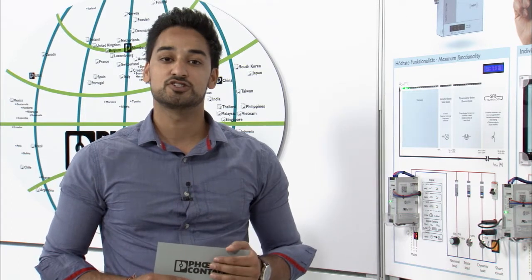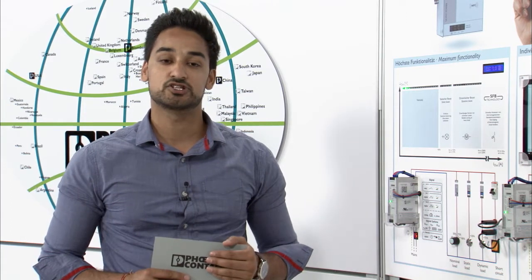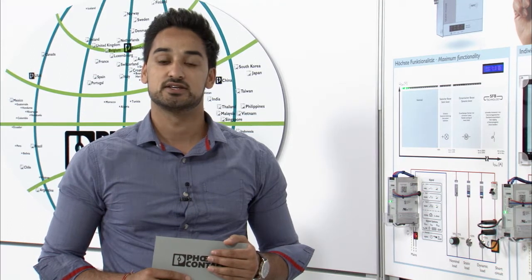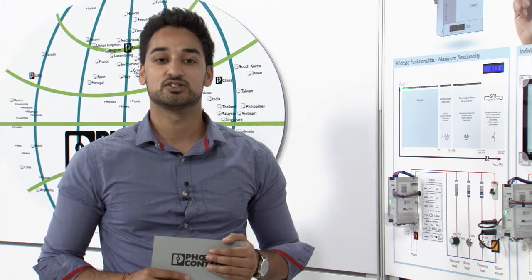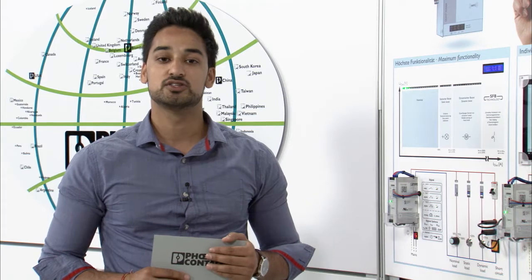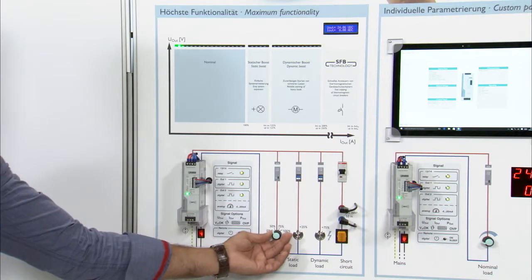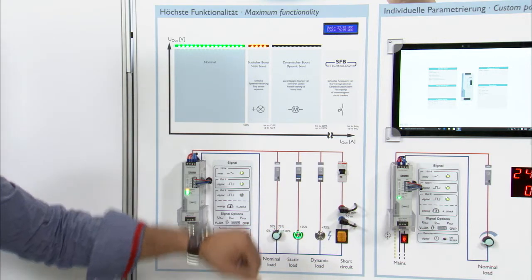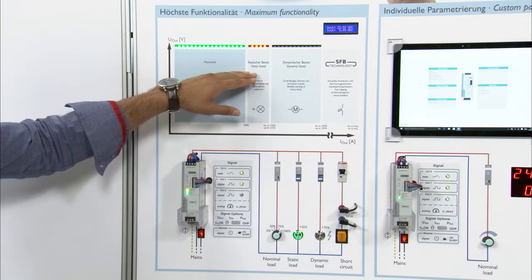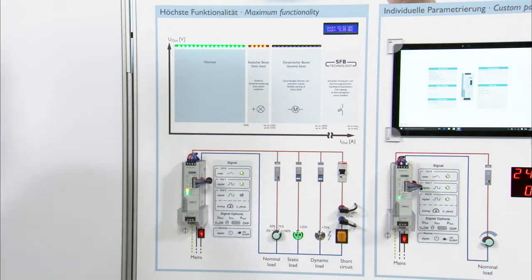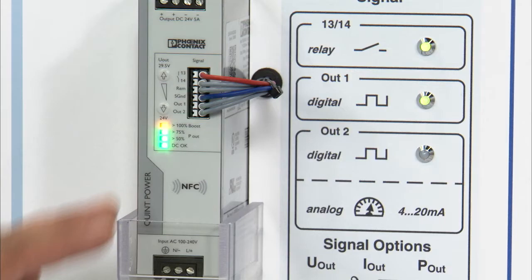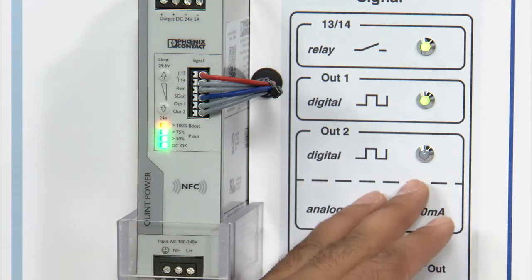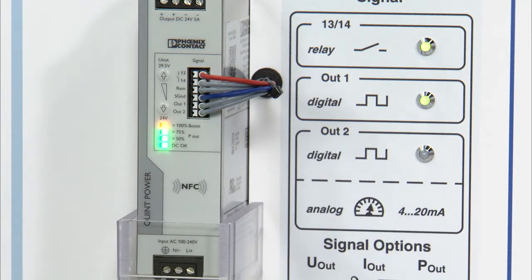The new Quint Power of the 4th generation has an adjustable threshold and gives you a pre-warning to prevent such a case. The default setting of the signal contact Out 2 is to monitor the nominal power. So if you increase the output power and exceed the nominal power due to system expansion, then on the one hand the static boost means the Quint Power will still securely supply your system, and on the other hand the Quint Power will give you a pre-warning that your application has exceeded the limits of nominal power. You can also set a different threshold.